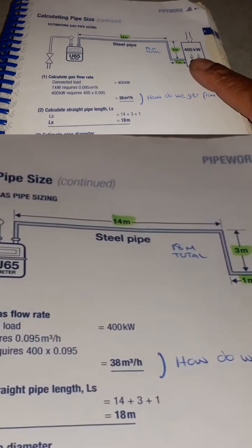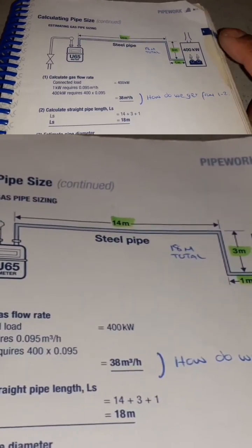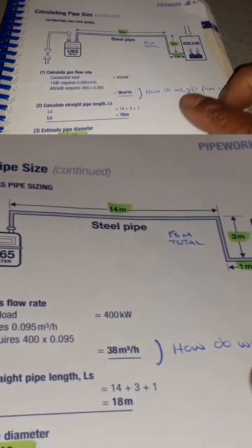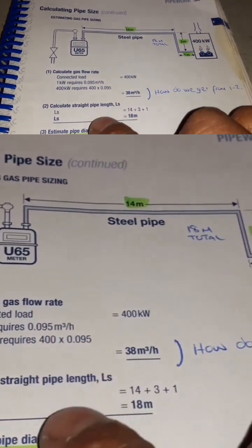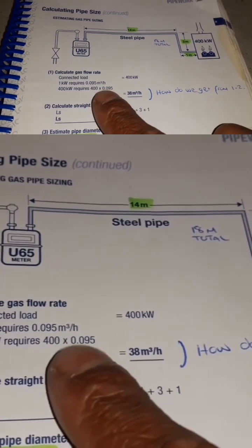We need to find out what size of pipe we need in order to supply the right flow rate. As you can see in this book here, it says calculate gas flow rate - connected load: one kilowatt requires 0.095 meters cubed an hour of gas.